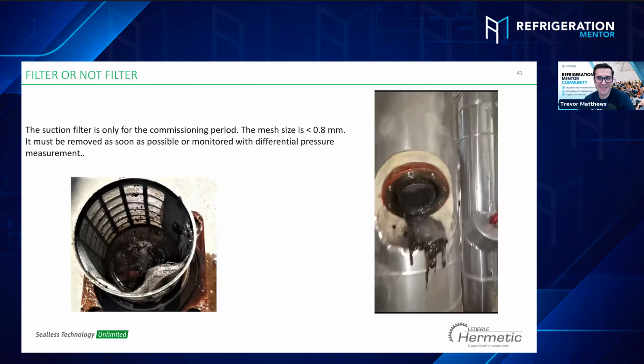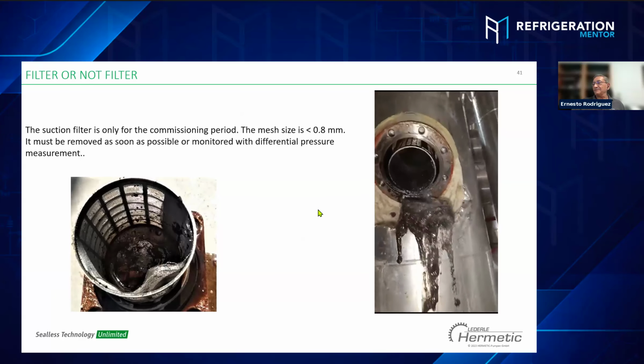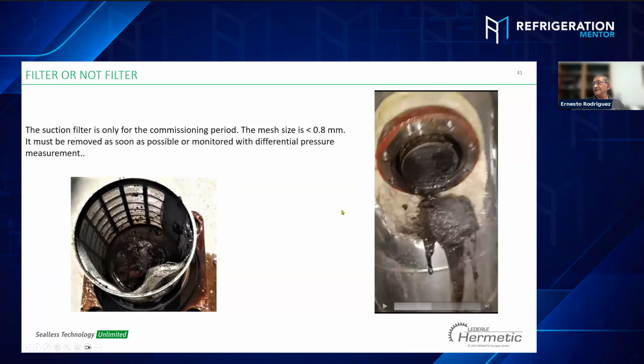Okay, talking about ammonia, we have this problem that looks like typical ammonia oil. I had a customer call me saying the pump is not increasing any pressure. I said check the filter, remove it, and see what you see. Send me the video and the oil. We go a little to the side, from CO2 to ammonia. In ammonia we have this big problem: this filter collapsed because of the oil. We need to be careful installing filters for ammonia. You can install a filter for CO2 because it's cleaner, but you need some type of monitor on the differential pressure, to prevent the differential pressure on the filter from increasing and damaging the suction of the pump.